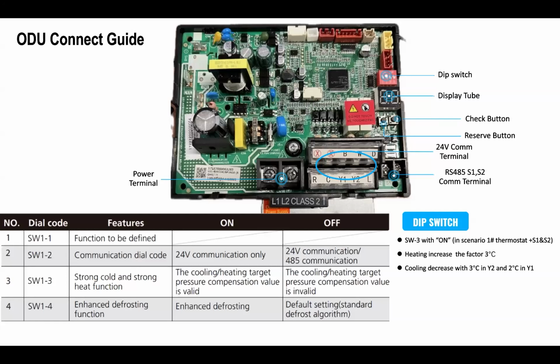Like I said, if you do full 24-volt communication, you've just taken our machine from a 19-SEER down to a 14-SEER on-off machine. So we always want S1, S2 communication. The reason I'm discussing this is because somewhere along the line, somebody's going to have an emergency on a Friday night and need to get somebody's heater or air conditioning going. It's that simple. Other than that, I don't recommend it at all.